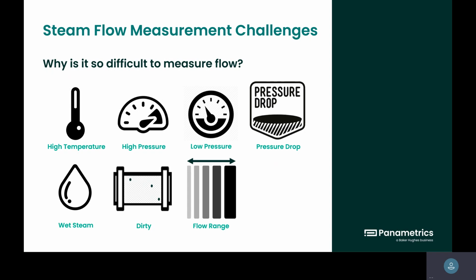Flow range. When we talk about steam measurement, obviously my ideal application runs in the nominal range. Well, you also have upset conditions, and you also have lower usage conditions, just based on how you're using it, whether it's refineries, district energy, or power. The amount of usage is going to be variable, so it's a discussion you always need to have when talking about steam flow measurement. And when we talk about flares, obviously high demand systems mean more steam. So that rangeability needs to be there for that type of measurement, whether it's using two or three different elements, or you want to use one element to cover it all.